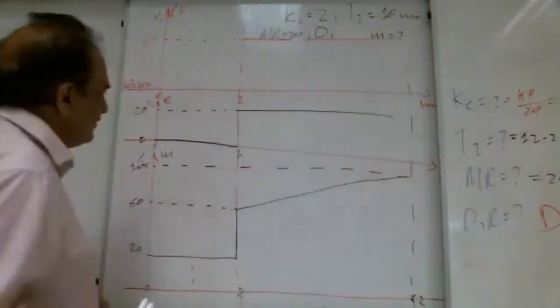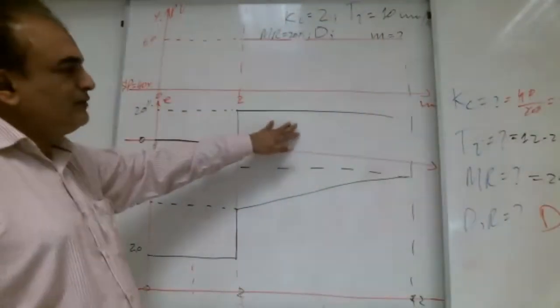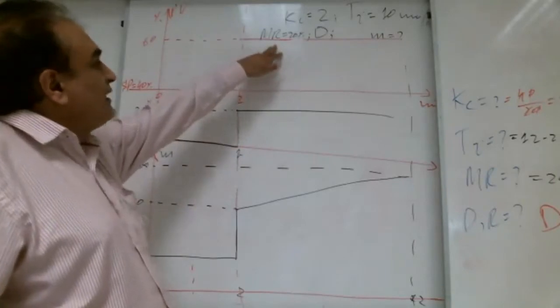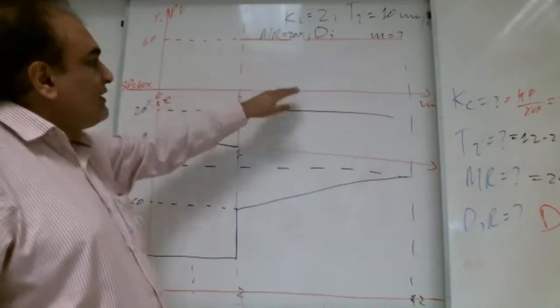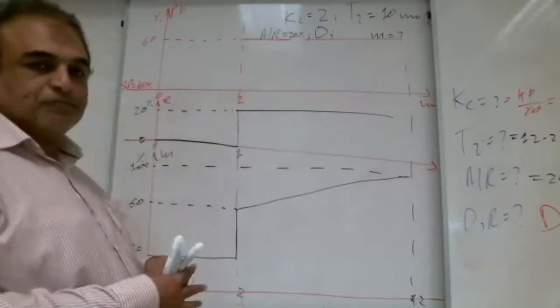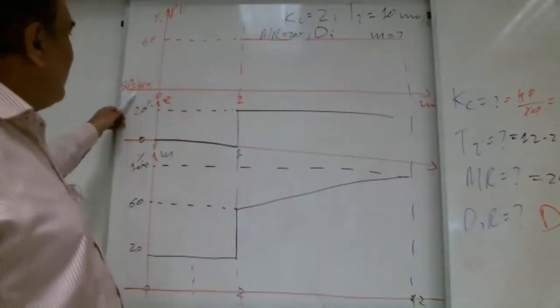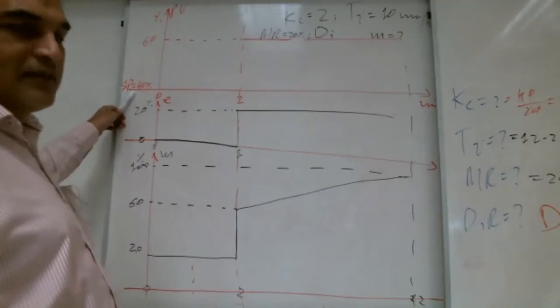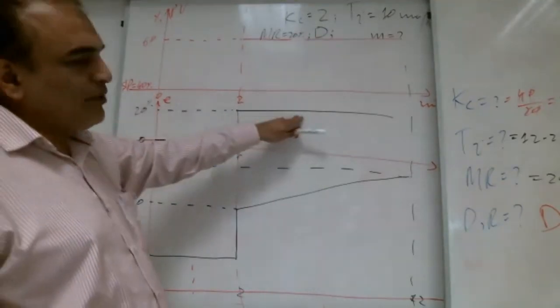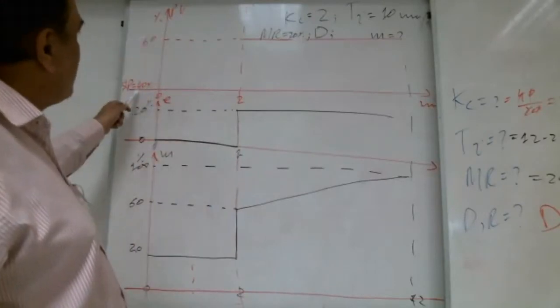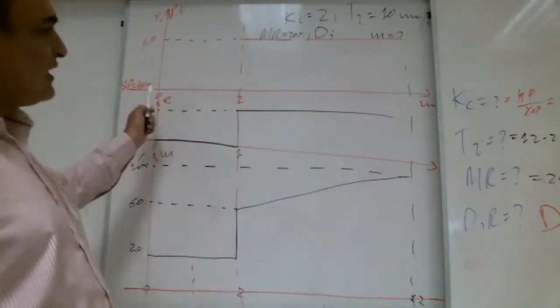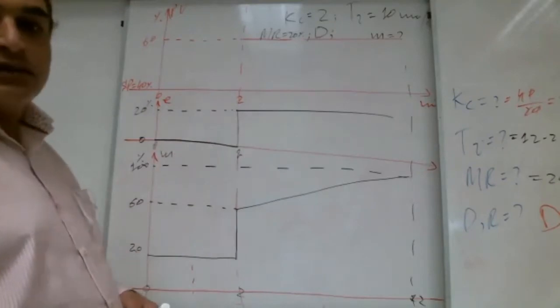Once again, Shabab, see, error is positive. PV is bigger than, what is PV here? 60%. What is SP? 40%. So PV is 60%, the set point is 40%. That error is 20, positive. So it means action is direct. You can say 60 minus 40, so PV minus SP. So action is direct.